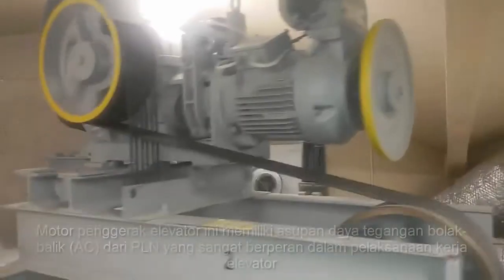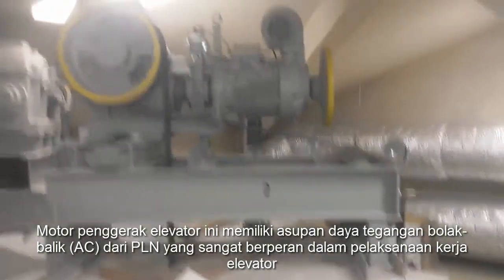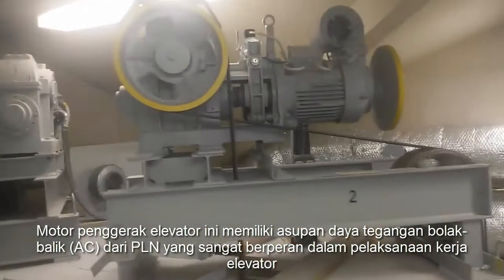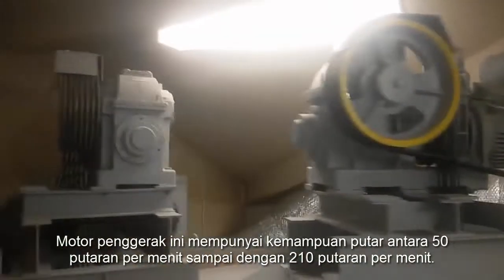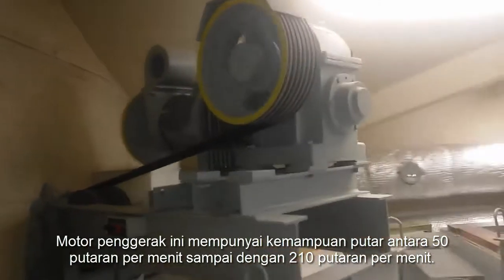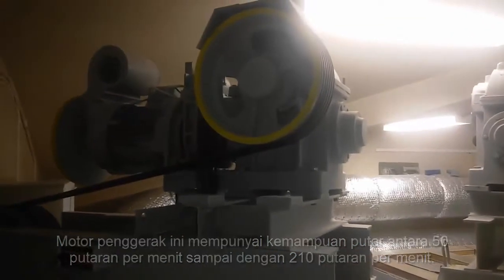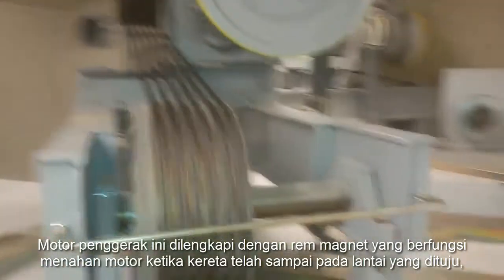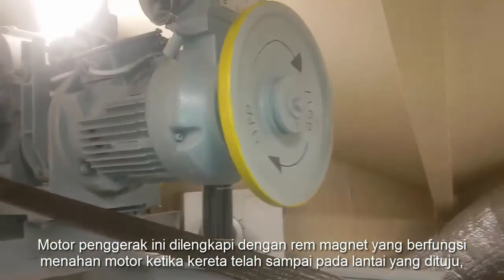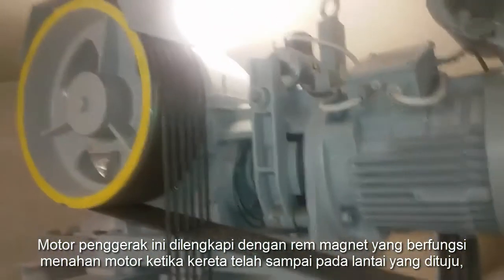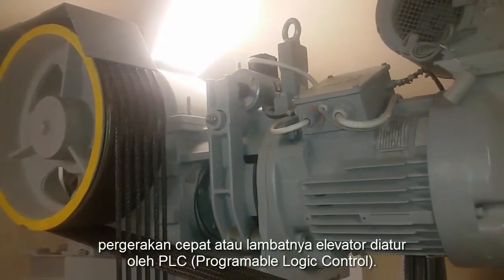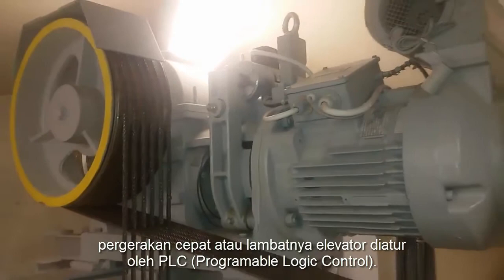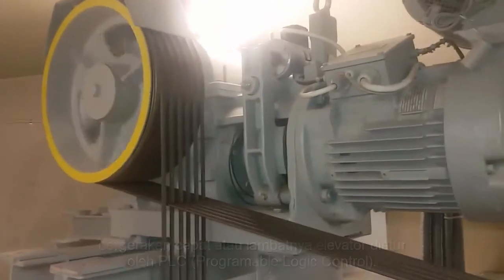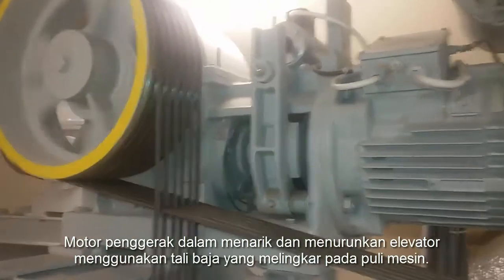Motor. This elevator motor has an alternating current AC power supply from PLN, which is very important in the elevator's work. This motor driver can rotate between 50 and 210 revolutions per minute, with a motor voltage capacity adjusted to the carrying capacity. The motor driver is equipped with a magnetic brake which holds the motor when the car has reached the intended floor. The movement of the elevator, whether fast or slow, is regulated by a PLC, Programmable Logic Control. When pulling and lowering the elevator, the motor driver uses a circular rope on the pulley of the machine.